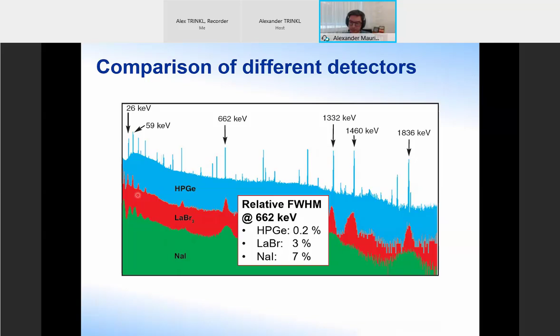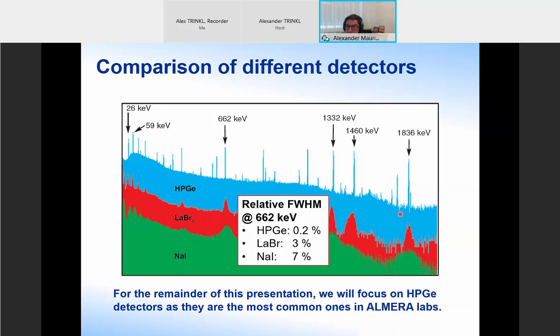There is also an energy effect, so peaks at higher energies will tend to be wider than at low energies. I will not go through so much why this is. It has to do with what kind of noise effects contribute to the resolution, but it is good to know that you might have a very small resolution value at the low energies and then quite a bit larger one at the higher energies. So for the remainder of this presentation, considering that high purity germanium is the golden standard here, as we have just demonstrated why, we will focus on those types of detectors for a bit. And also because these are the most commonly used type of detector in Almera laboratories.